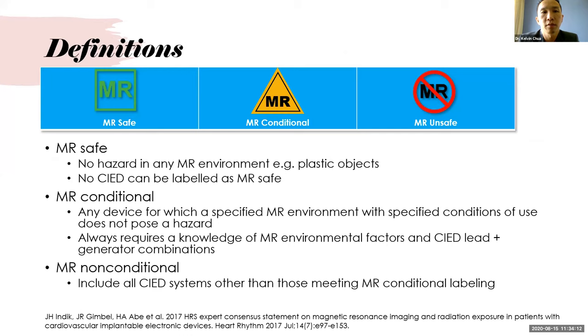Some definitions to make sure we're clear: no cardiac device can be labeled as MRI safe. MRI safe labeling requires the object to pose absolutely no hazard in any MR environment—an example would be plastic objects. An MR conditional device is one that has been tested in a specific MR environment with specified conditions and proven not to pose any hazards. This often requires combined knowledge of MR factors and the device's lead and generator specifications. An MR non-conditional system includes any devices other than those meeting MR conditional labeling.